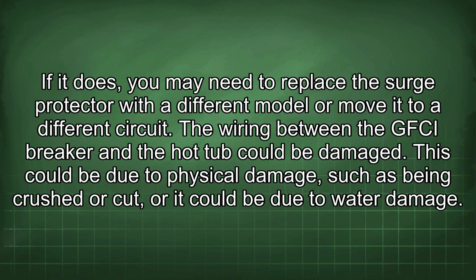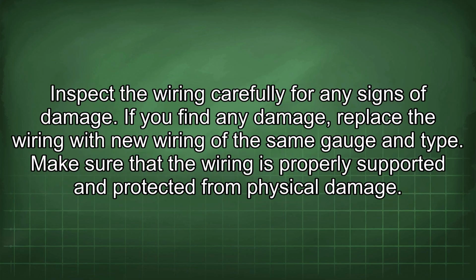The wiring between the GFCI breaker and the hot tub could be damaged. This could be due to physical damage, such as being crushed or cut, or it could be due to water damage. Inspect the wiring carefully for any signs of damage. If you find any damage, replace the wiring with new wiring of the same gauge and type. Make sure that the wiring is properly supported and protected from physical damage.